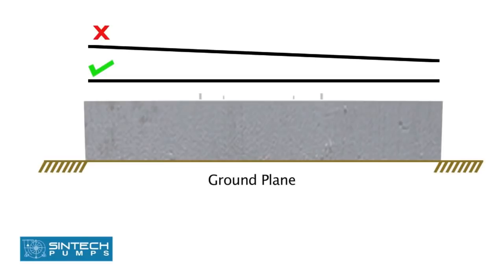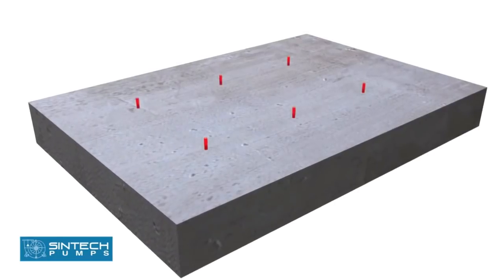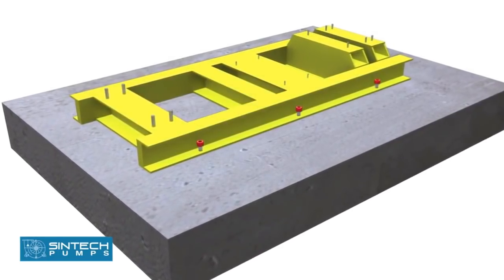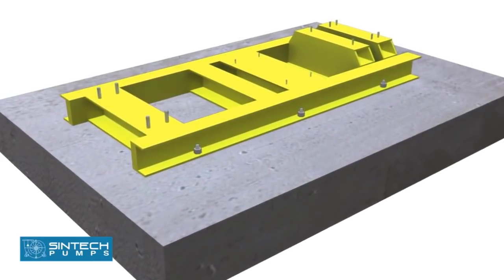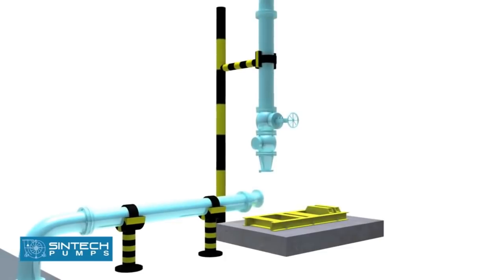The foundation bolt of proper size should be embedded in the concrete and baseplate tightened, ensuring that it is level in all directions. Piping associated with the pump must be anchored and supported independently of the pump and should never put any strain on the pump casing.